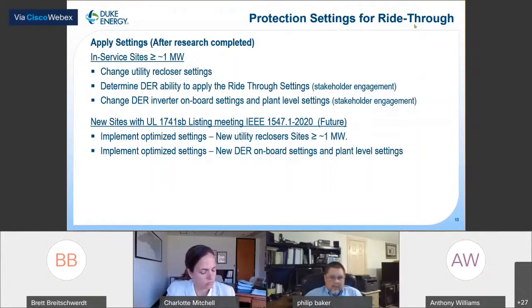We also have to find out the ability of the in-service DER equipment to accommodate new settings. One way to do that may be to look at the old 2003 standards and see if our optimized settings fall within the bandwidth of the requirements from that era. If they do, then it's almost certain these devices will be able to accommodate the settings.